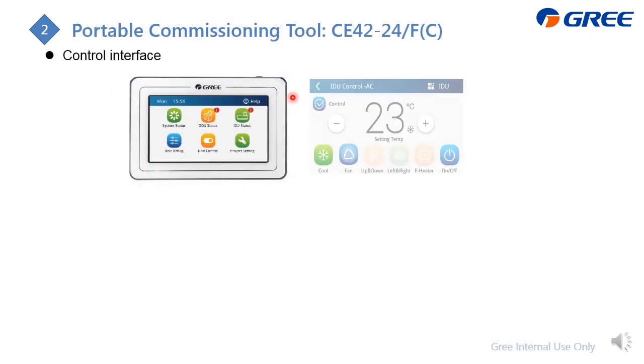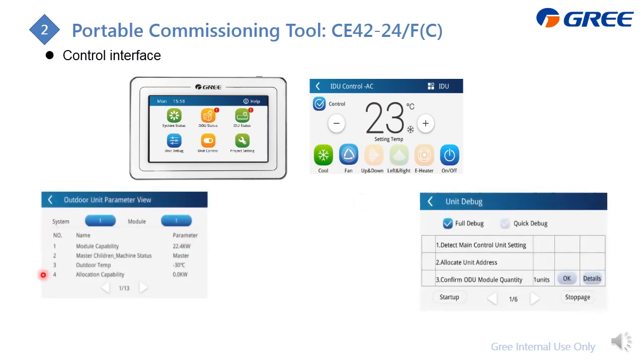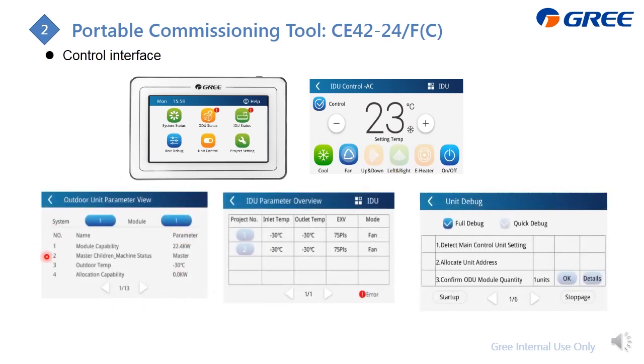As for the portable debugger, which is this one, this is the control interface of the specified indoor unit. And also the same, you can change the setting temperature, mode, fan speed, and how the louver swings. And also you can check all the outdoor unit and indoor unit information. And also if you choose debugging from here, we will display all the steps directly here for you. And currently this quick debug is reserved, no function.